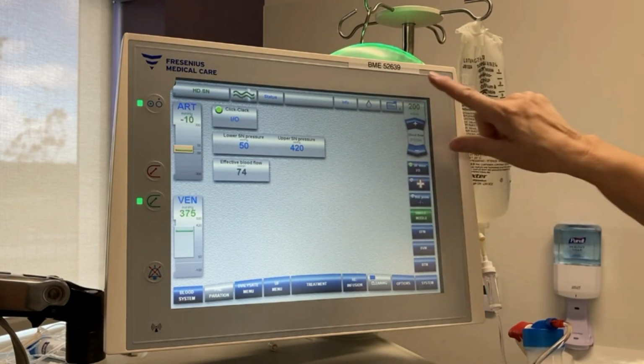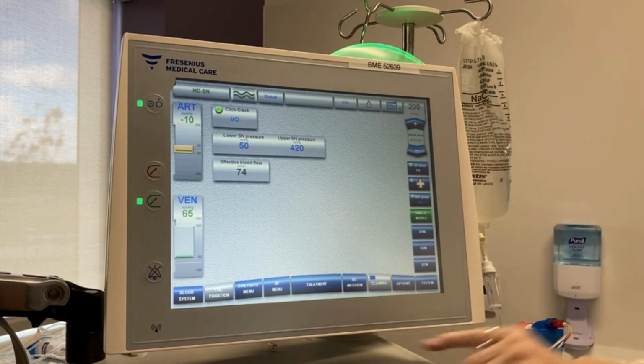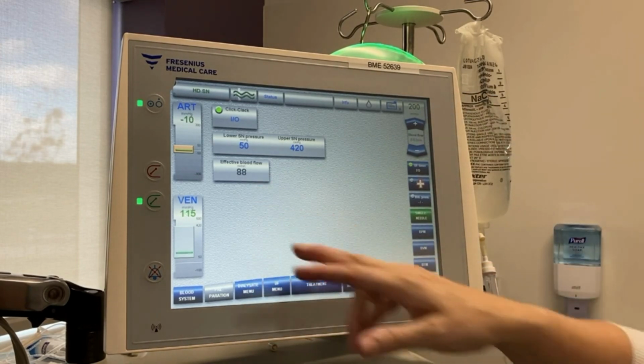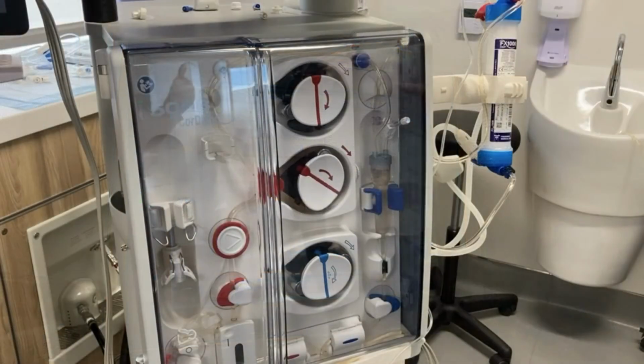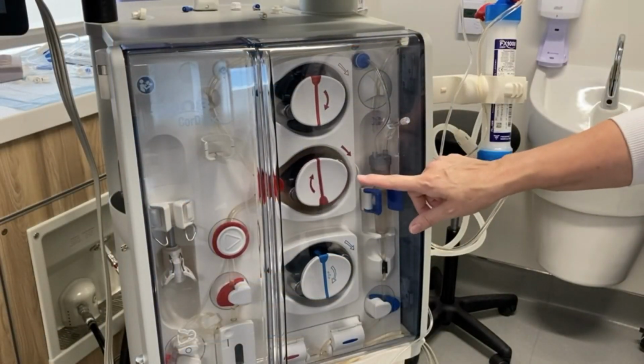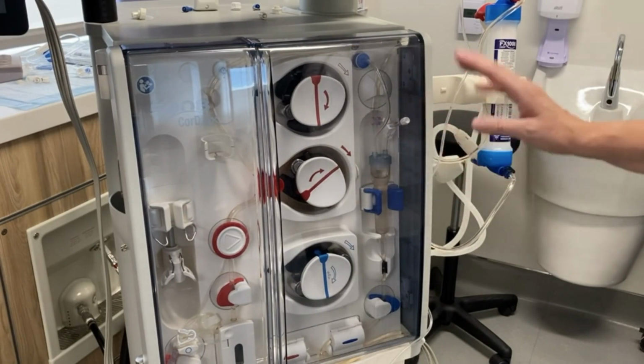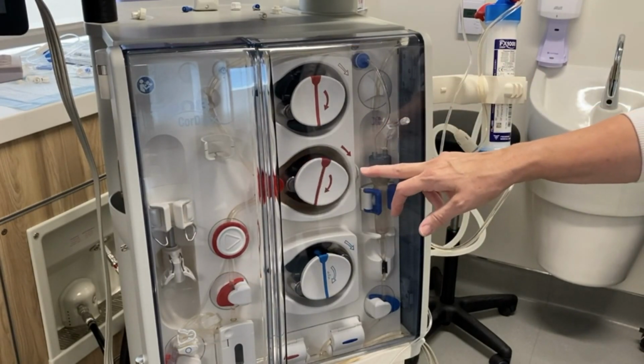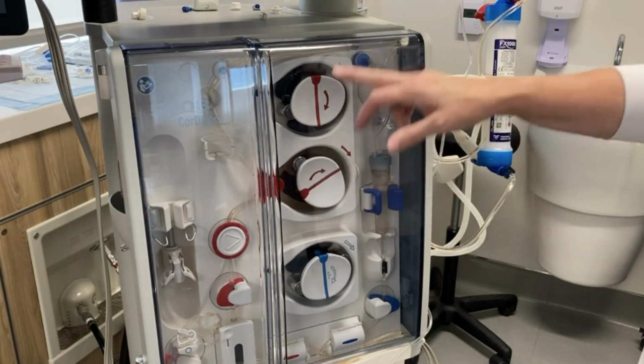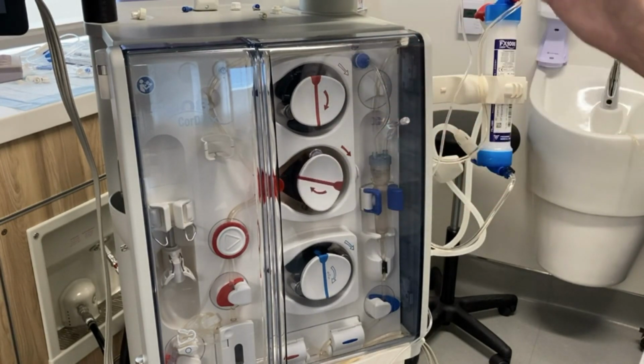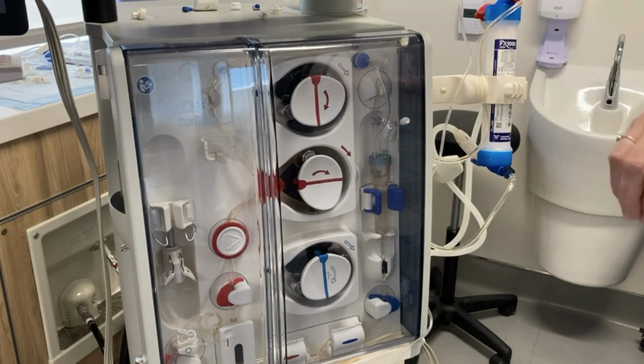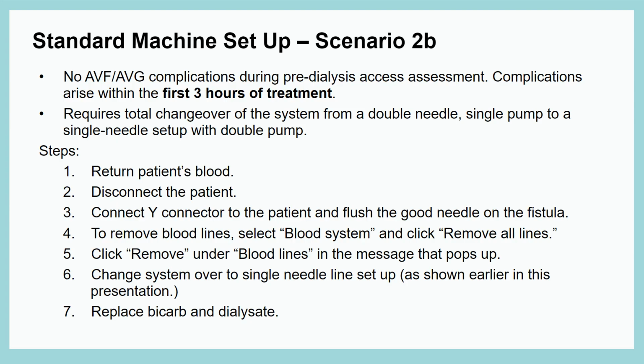Okay, so we increased the pump speed to 200, which is giving us an effective blood flow of around 88. And you'll see down here that the pump is just stopping and starting. So this is, as it's pulling from the arterial, it pulls, and then it'll stop and then return to the venous.